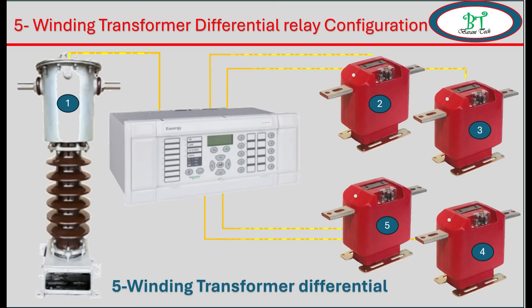Now I am going to focus on the numerical relay. The main protection is known as transformer differential protection. Since this is a five-winding transformer, we need five CTs with a three-phase set for this protection — one from the HV side and four from the LV side. Before going into relay settings, we must understand this concept. Let us consider the transformer rating is 8000 KVA.